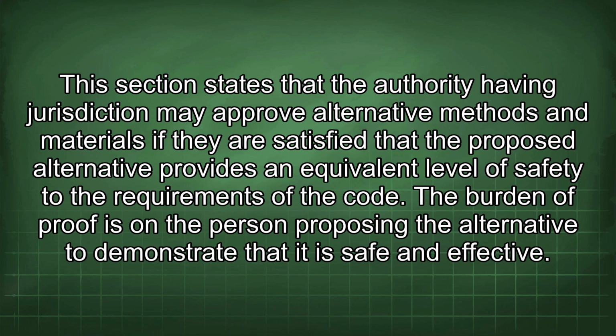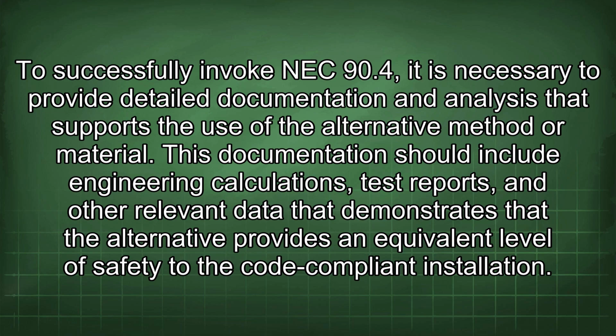The burden of proof is on the person proposing the alternative to demonstrate that it is safe and effective. To successfully invoke NEC 90.4, it is necessary to provide detailed documentation and analysis that supports the use of the alternative method or material. This documentation should include engineering calculations, test reports, and other relevant data that demonstrates that the alternative provides an equivalent level of safety to the code-compliant installation.